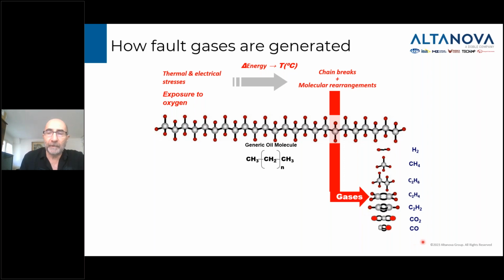The other gases that are generated in normal operation are carbon dioxide and carbon monoxide, and both gases come mostly from the continuous degradation of your insulation paper. Those gases usually continuously increase over time as your insulation paper continues degrading during the life of the transformer. Now, the other gases that we're looking at in the DGA, the methane, the ethane, the ethylene, and especially the acetylene, are normally not created in the normal operation of a transformer. Those gases are created when a thermal or an electrical fault starts developing.